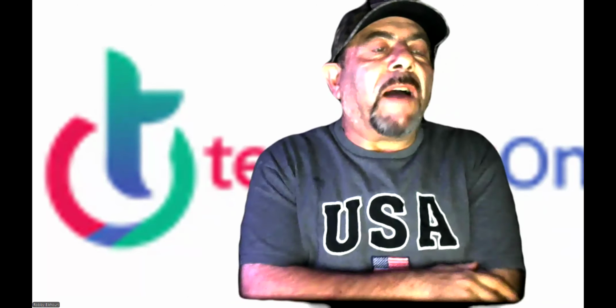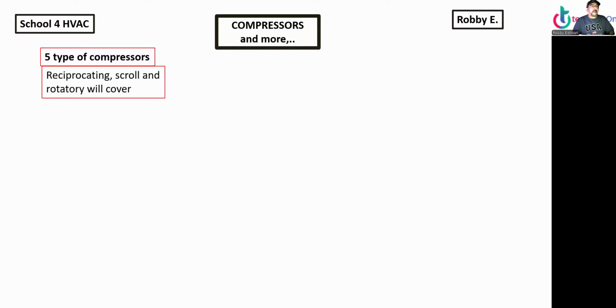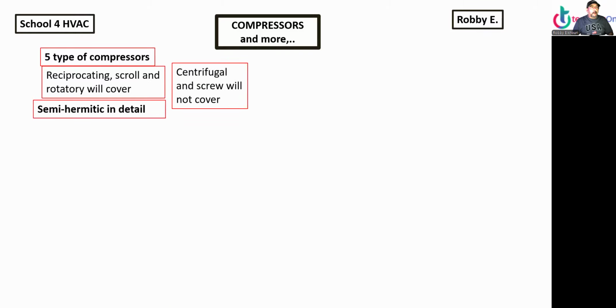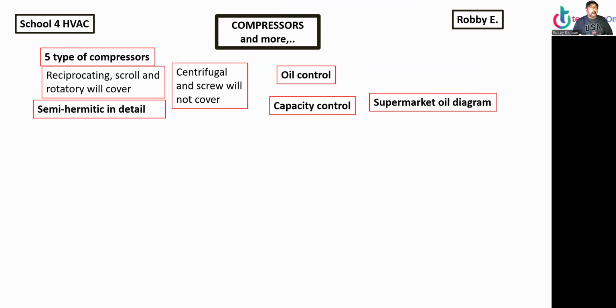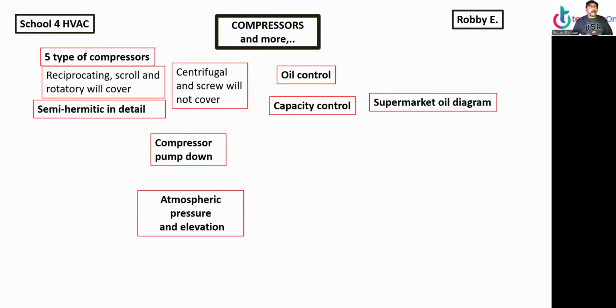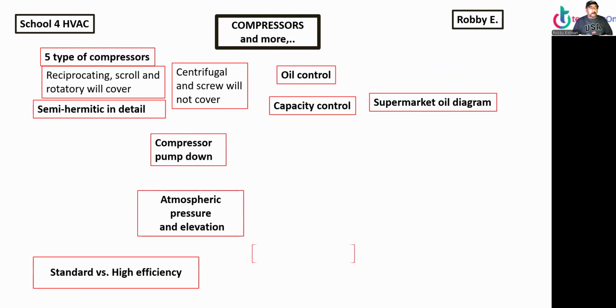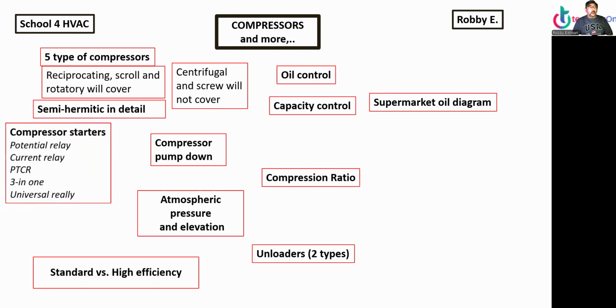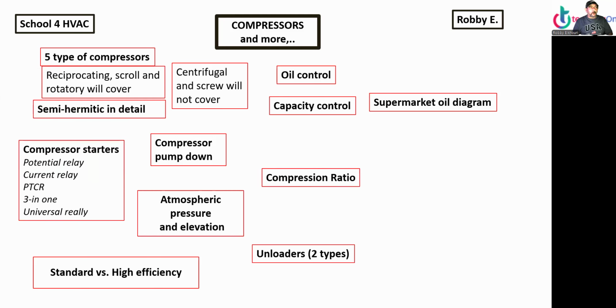Alrighty. So five types of compressors I'm gonna cover. The reciprocating, scroll, rotary, I will cover. Semi-hermetic in detail. Centrifugal and screw, I will not cover, just a quick video. Then I'm going to also go with oil control, supermarket oil diagrams, capacity control, compressor pump down. That's how we check if it's broken or not. I'm going to talk a little bit about atmospheric pressure and elevation, standard versus high efficiency. That's system. Unloaders, two types. Compression ratio. I'll talk about the compressor starters: the potential relay, current relay, PTCR, 3-in-1, and universal relay.